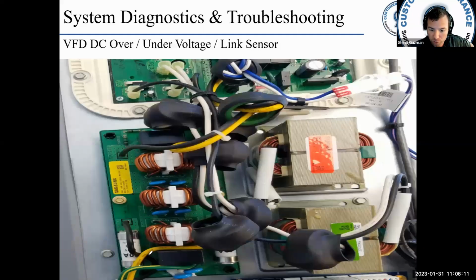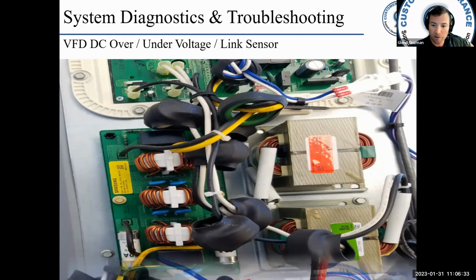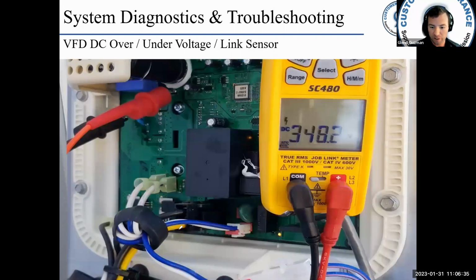and it goes to the filter board. Okay, here's one. It goes through this filter board. There's a couple fuses here, kind of hard to see, but there are fuses on this filter board. Okay, it goes through the filter board and out of the filter board up to the VFD. Okay, so you want to make sure the voltage is getting into the filter board, out of the filter board, and eventually up to the VFD. You can see the yellow and black plug right here.